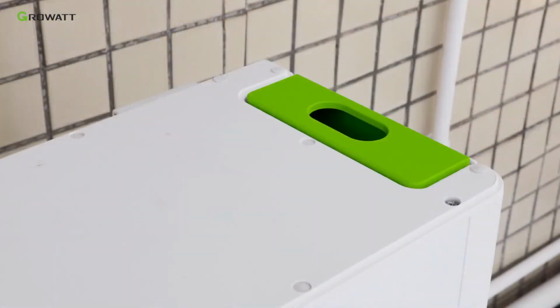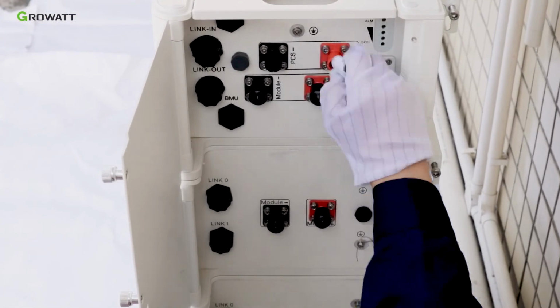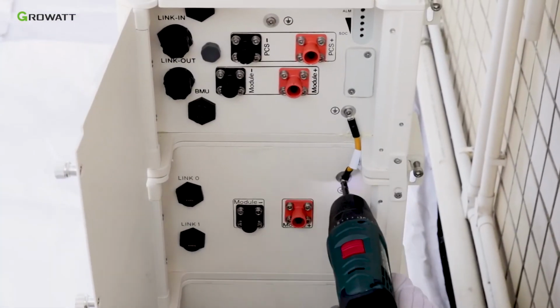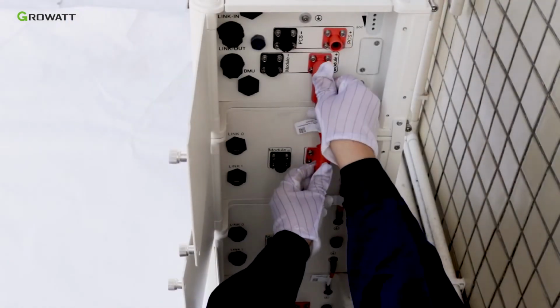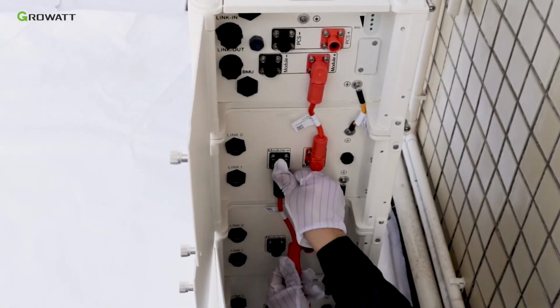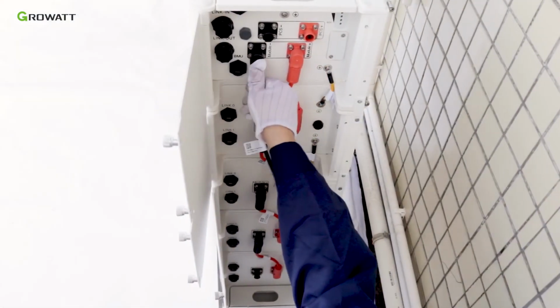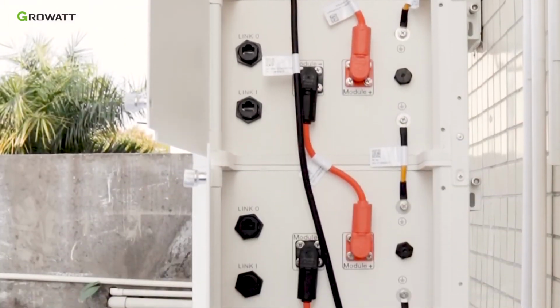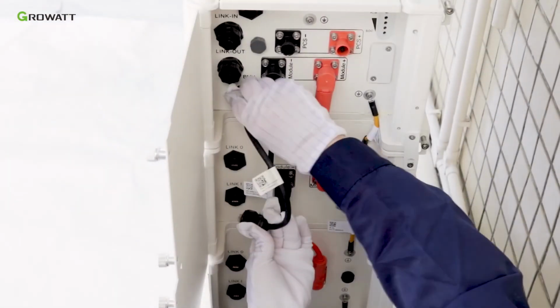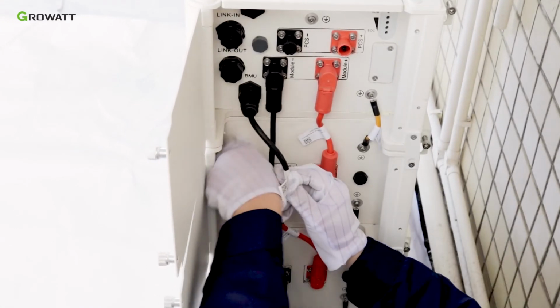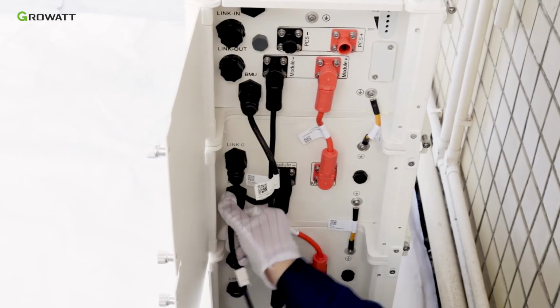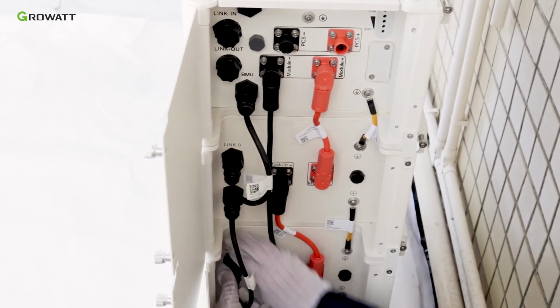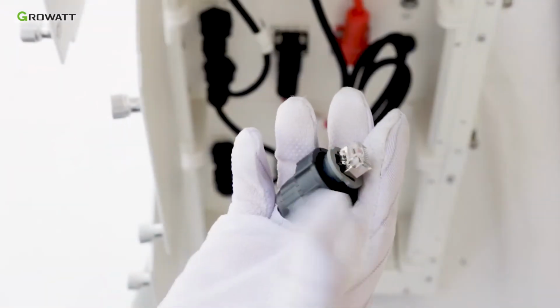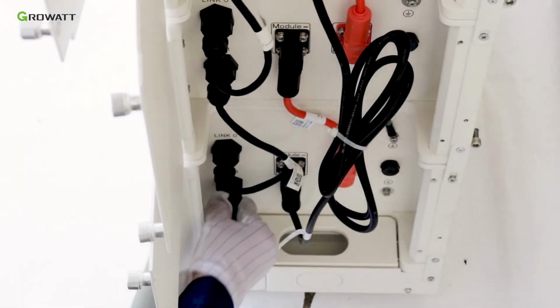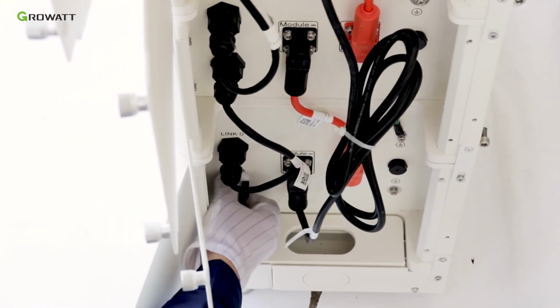Please don't remove the partial top cover of the power module. Remove the dustproof covers attached to the battery pack. Connect the ground cable between battery packs. Connect the positive and negative power cable in series between all the battery packs and the power modules. Connect the communication cable from the BMU port of the BMS module to the link 0 port of the top battery pack, and connect all the battery packs one by one. Notice: please remember to connect the single plug connector to the link 1 port of the bottom battery pack.